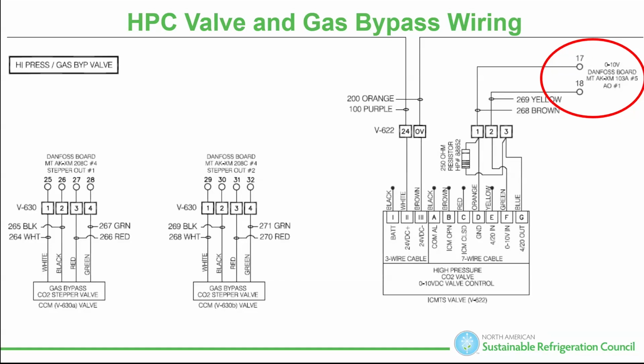And then I take my lead back to the red, green, and red, and I want to replicate that. I'm going to see the same thing. If you've never done that and you're at the rack, next time you're at a stepper valve, try it. It works with the CCMT, the CCM, it works with the SCRs. I do it all the time just to prove my theory because it's something you want to see. Think about it. Every time it steps, it's got a signal, and you can read that signal with your DC meter.